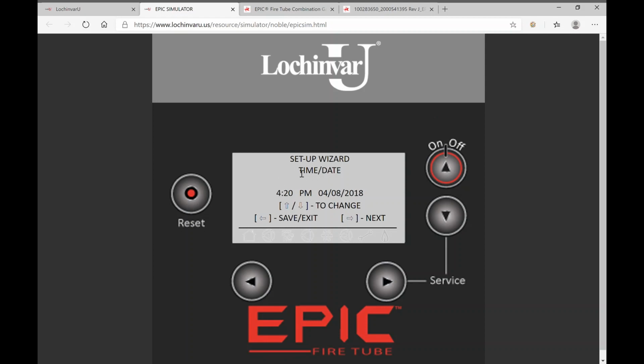The first thing we see is time and date, and we can adjust this by the up and down arrows on the right side. Once we get that to the correct time and date, we can push the next button on the lower right hand side, and it takes us to our space heating set point on the coldest day. What that means is, when it's the coldest day outside of the year, what do we want our space heating set point to be? In this example it says 120, but it might be adjusted based on the different heat emitters that you have. An in-floor might be a little different, a radiator might be a little different, or an air handler might be a little different. So we have to determine, based on what we're actually heating, what we want that set point to be on the coldest day.